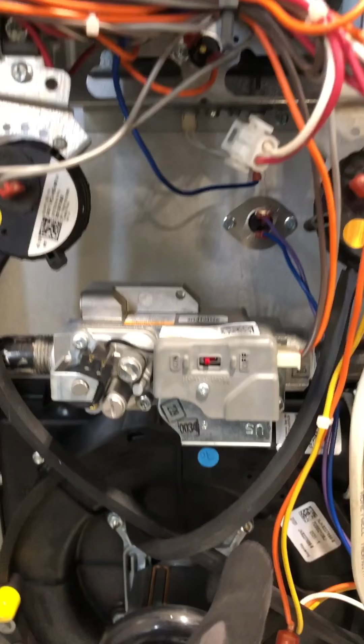Gas valve. This is powered by 24 volts. This controls the gas flow to the burners. Pressure switch. These guys have a 24 volt signal. They will open or close based on whether this motor comes on. So they're essentially a safety. We want this motor to come on. If it doesn't come on, this switch won't close and the furnace won't start.